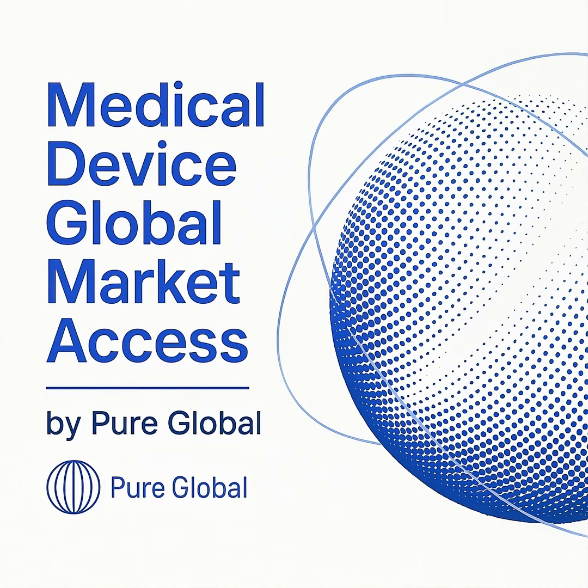The primary gatekeeper for an NSR study is the IRB. The sponsor must explain to the IRB why the device is considered NSR, and the IRB must review and approve the study protocol. Even without direct FDA submission, NSR studies must adhere to key provisions of Part 812, including labeling requirements, informed consent, monitoring, and specific record-keeping and reporting.